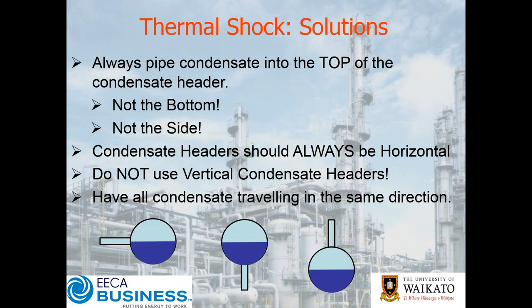What are the solutions? Always — and I did actually capitalize the word 'always' — always pipe condensate into the top of the condensate header. Never on the bottom and never on the side. Condensate headers should always be horizontal. Do not use a vertical condensate header. Have all condensate traveling in the same direction. We don't want a condensate header where the takeoff is in the middle. You want the condensate header on a slight incline preferably, so that it actually self-drains, and all the condensate heading in the one common direction.